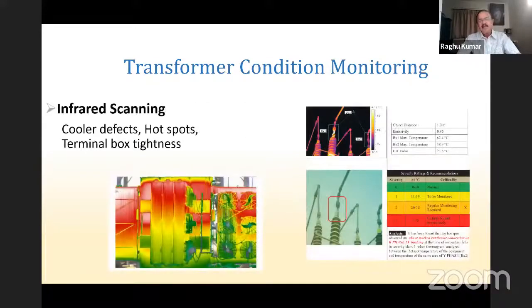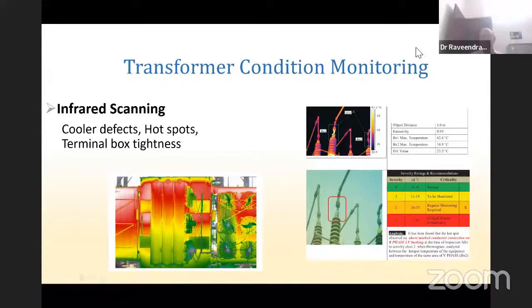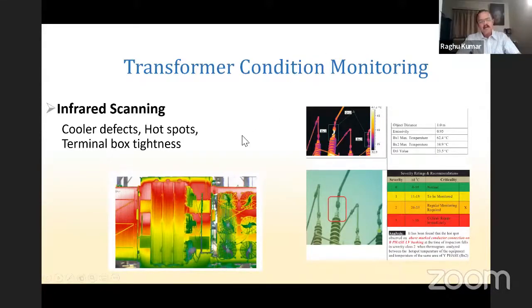Next comes infrared scanning. In infrared scanning, thermal images are taken using an infrared camera. This is normally done during peak load times. Normally in the Middle East, summer is the peak load.